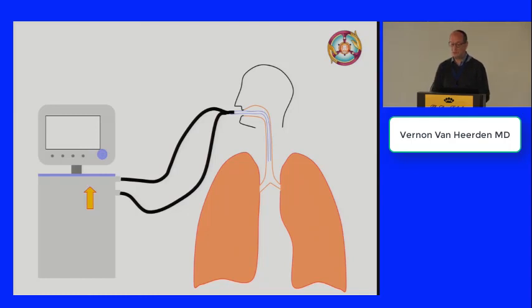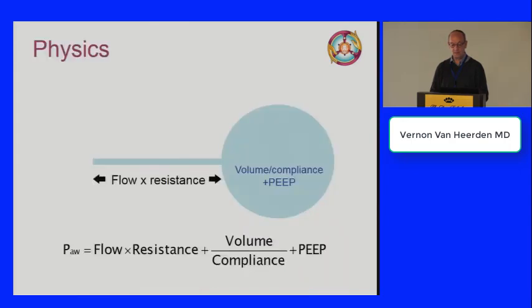Okay, as we've said already this morning, some of the ventilators measure the pressure actually in the ventilator, which is far away from where the pressure should be measured, which is in the trachea, but we need to be aware of that. So airway pressure problems might be because of inadequate or inappropriate ventilator settings, or measurement inside the ventilator which is not giving us an accurate reading. Okay, the physics we've seen already. So airway pressure is related to all those factors that you can see there: flow and resistance in the delivery tubes, volume, compliance, and PEEP within the alveoli.